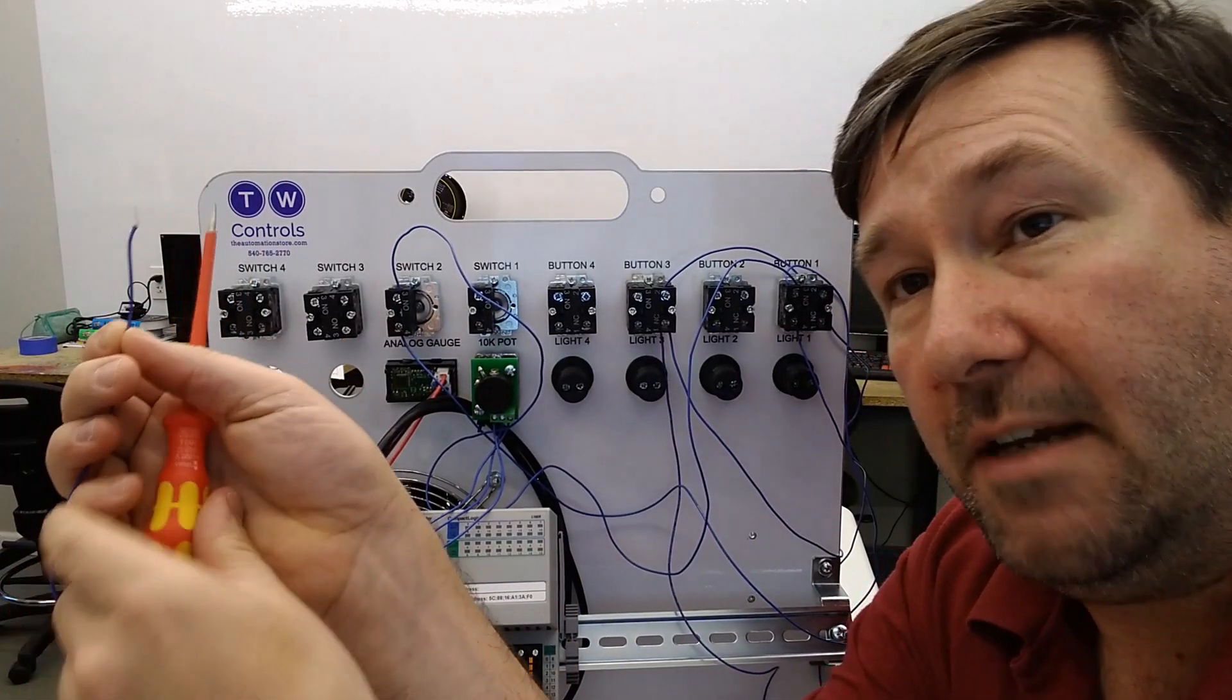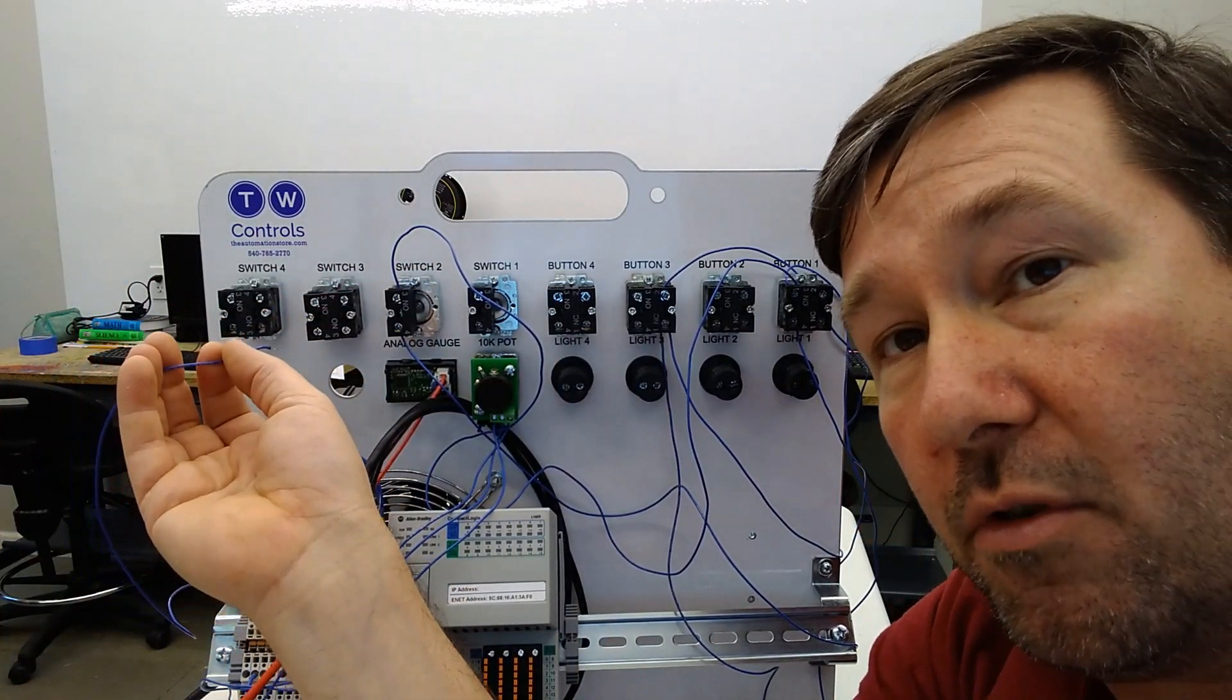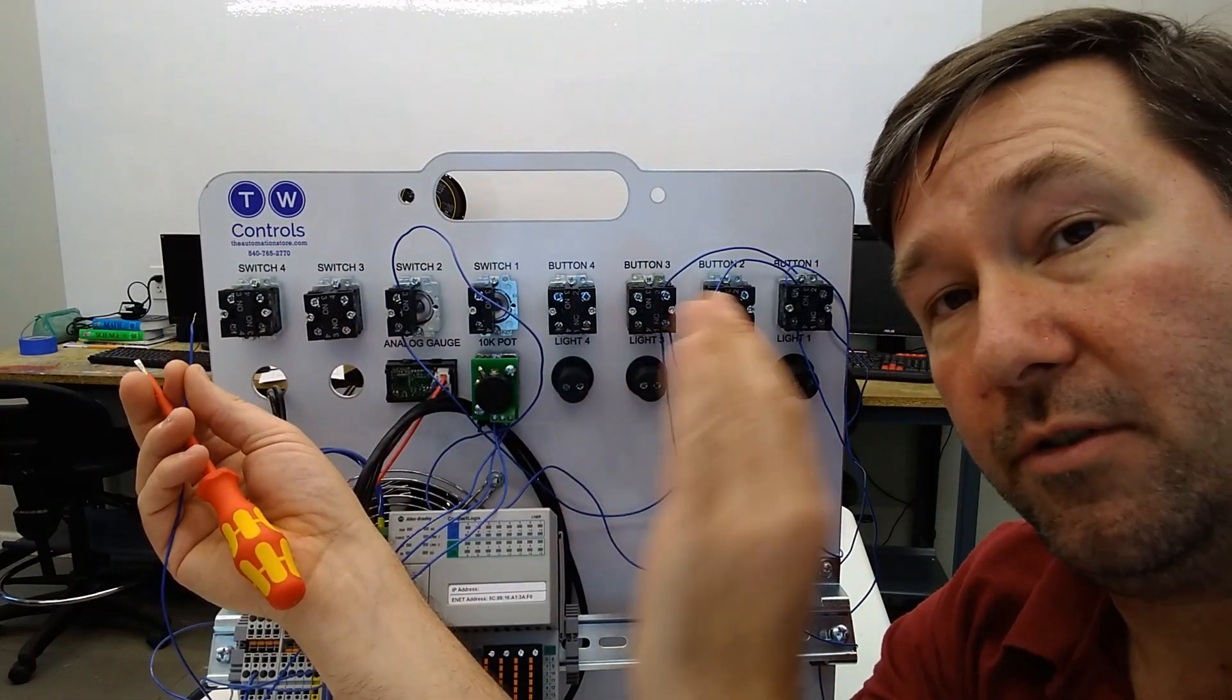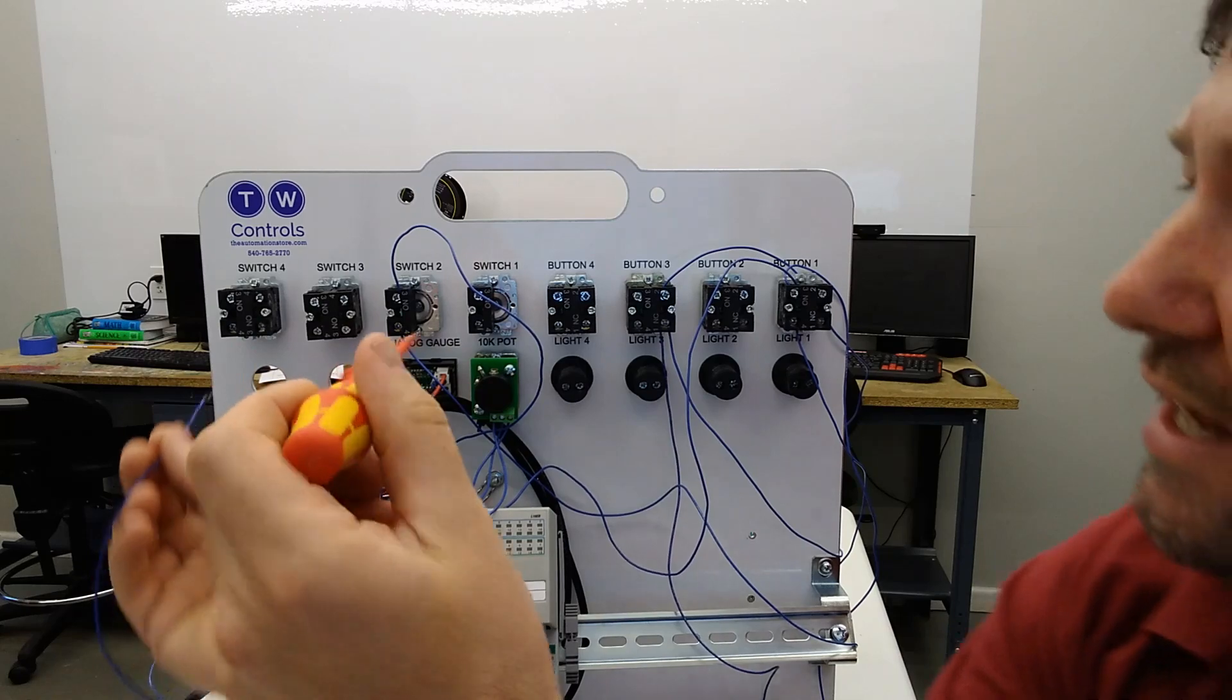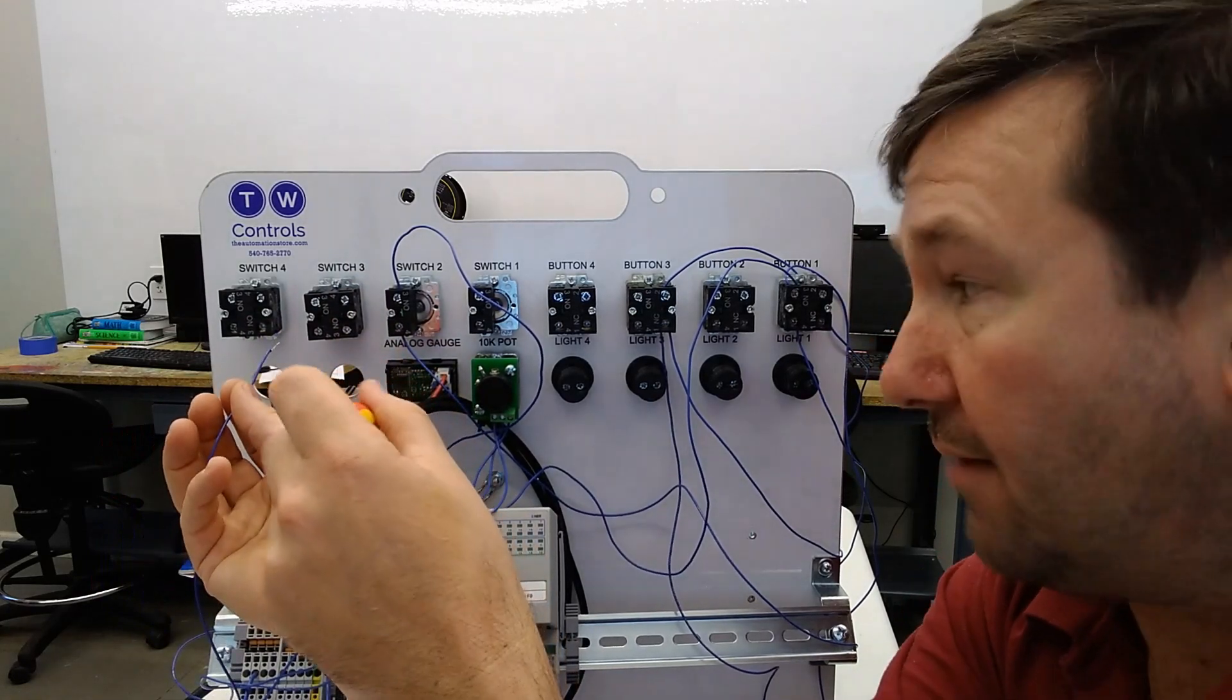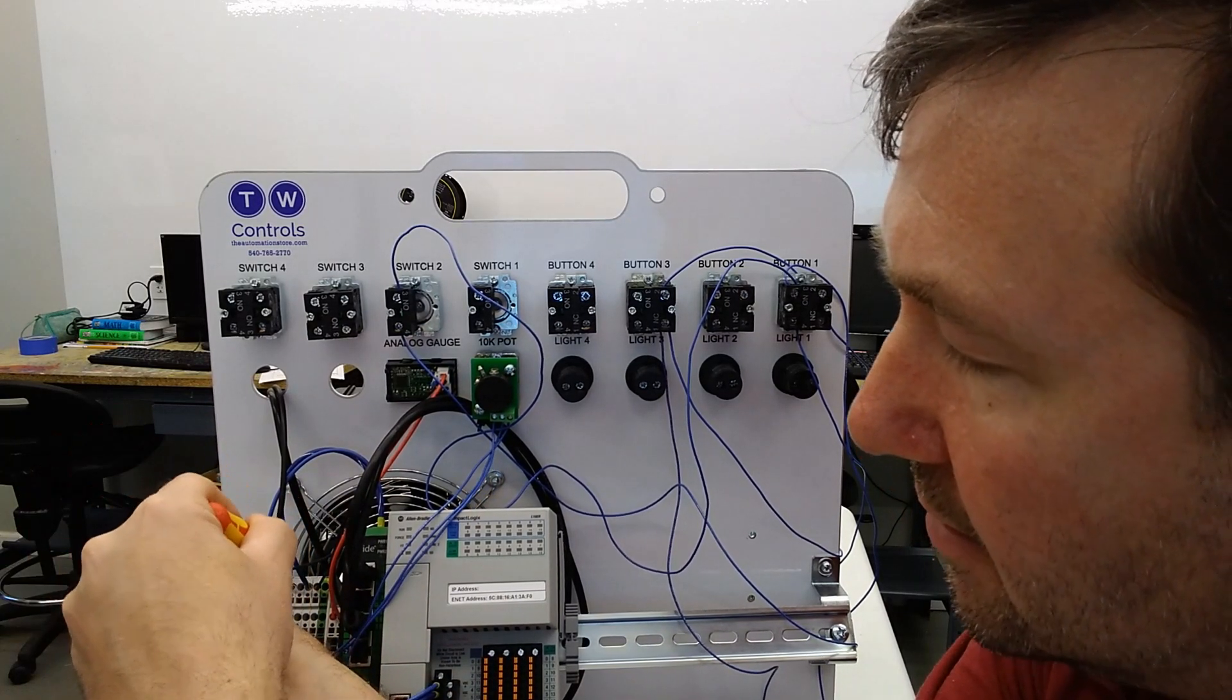Terminal 14, which is actually our common, we're not going to connect it up here to our meter. We're going to connect it to the common of our 24 volt power supply. That will make it where our 24 volt and the 10 volt on the drive references will be the same, or their zero volt point will be the same. The main reason we're doing it in this case is our analog gauge is powered by that 24 volt power supply, and that's what it references its voltage to. We'll connect it to the zero volt, which is the right set of terminal blocks.